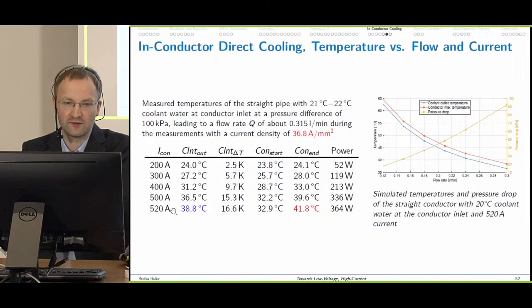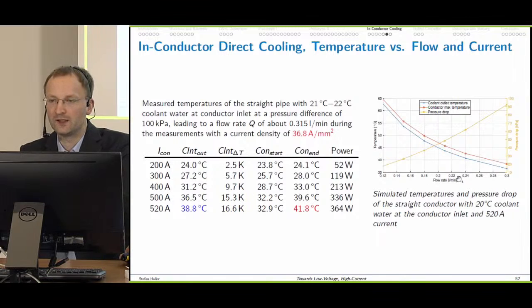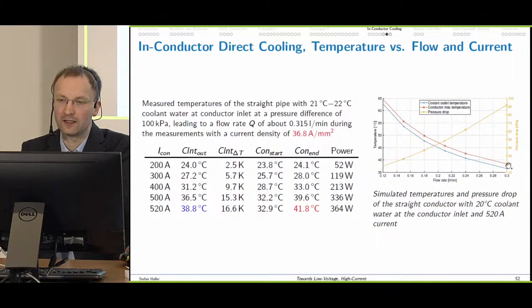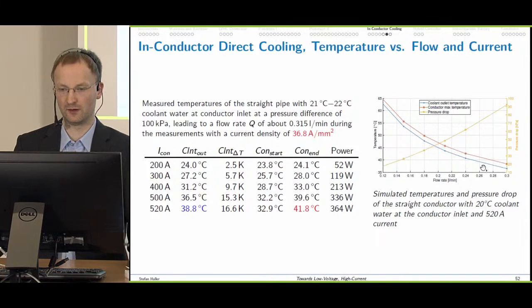What we could see here is at 520 amp, there's a good match of the coolant's outlet temperature to the simulated one, as well as for the conductor's temperature here. The reason why the measured values are a little bit higher is most likely from the massive copper clamps that we have and the heating from the feeding cables that reach about 70 degrees C. So if we go a little bit further away from the clamps, it matches a bit better.